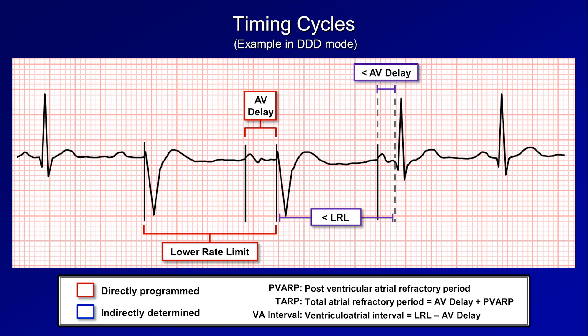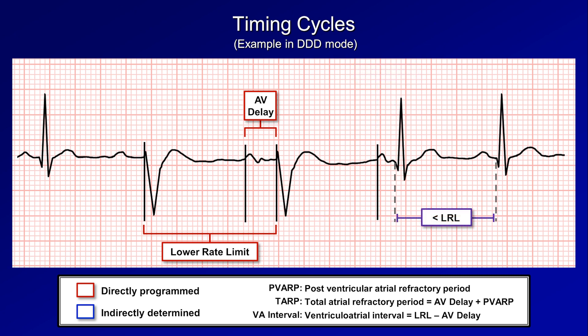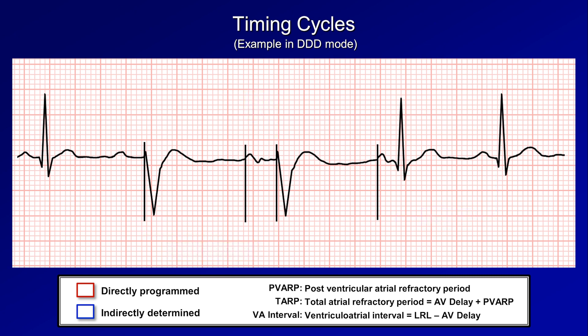With this final A-sensed V-sensed beat, it's the combination of both an intrinsic P wave and intrinsic AV conduction that leads to the shorter interval between ventricular depolarizations. With modern pacemakers and newer algorithms, timing cycles can be much more complex than this, but this is the basic idea of how settings impact the timing of cardiac events.